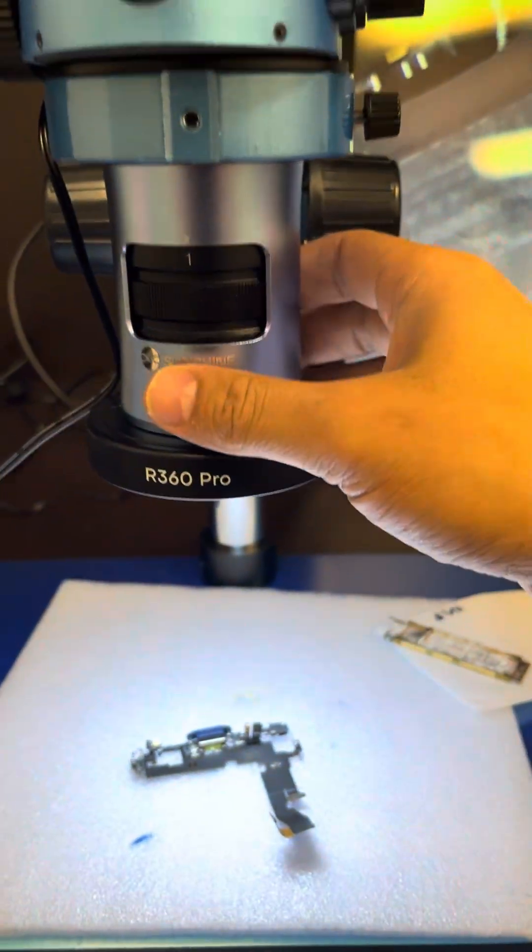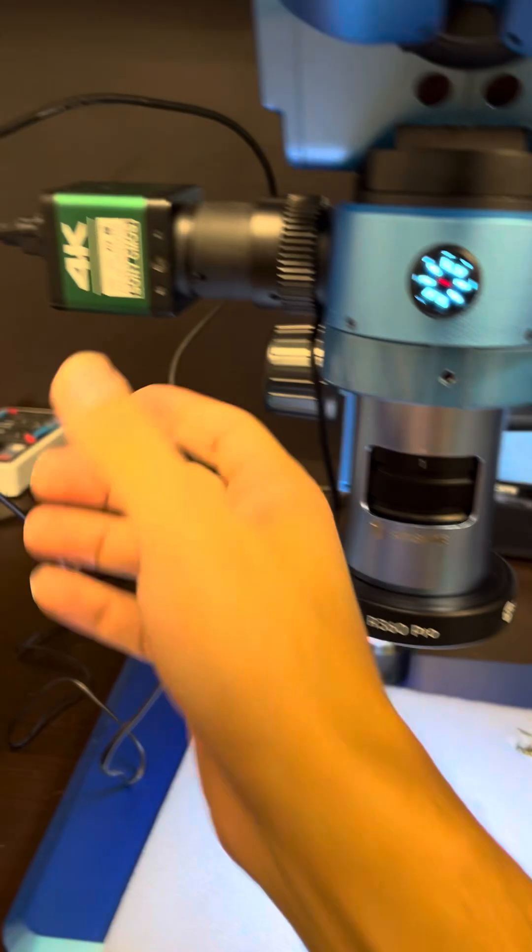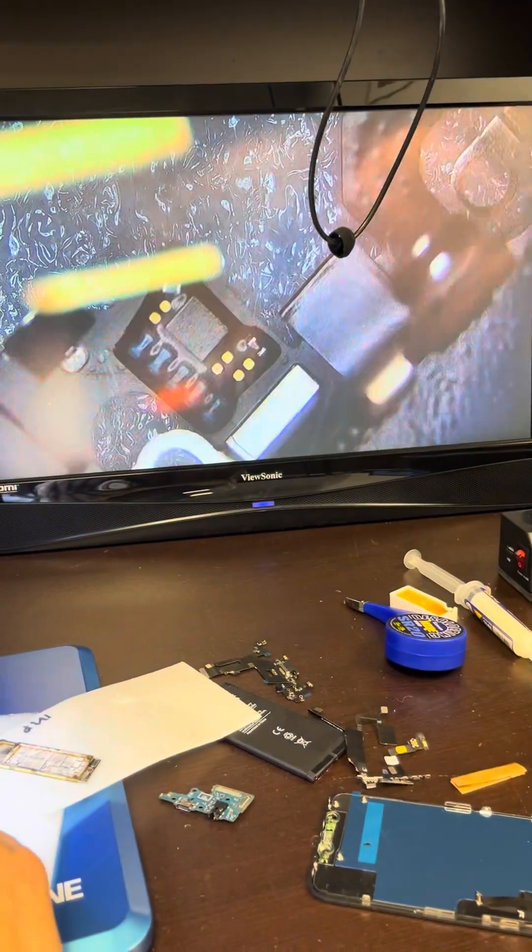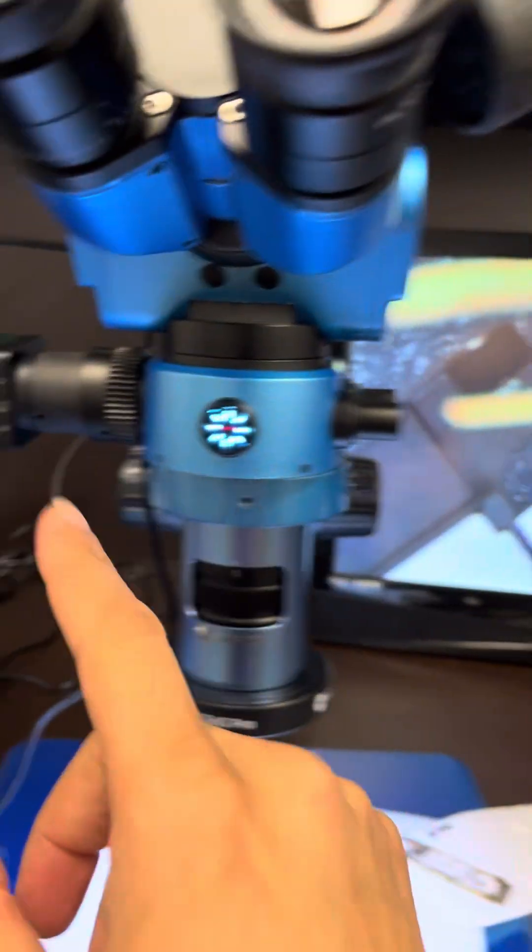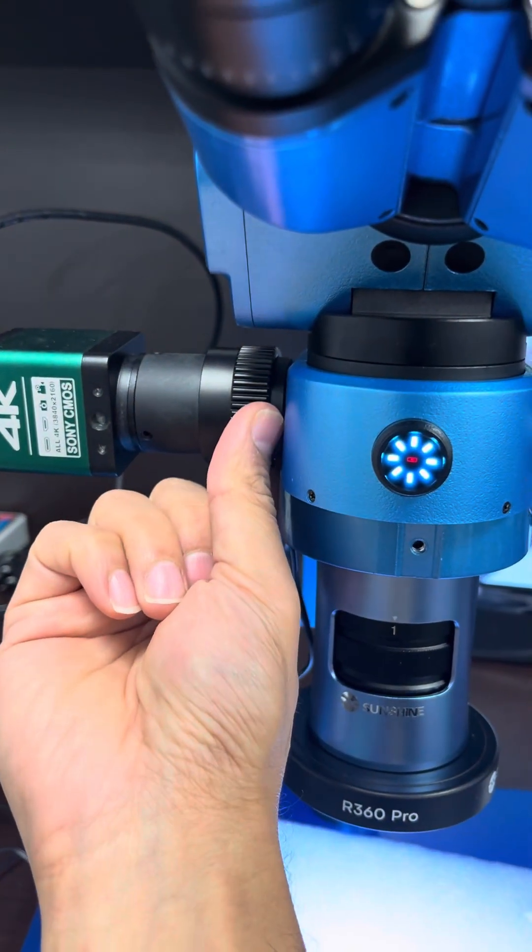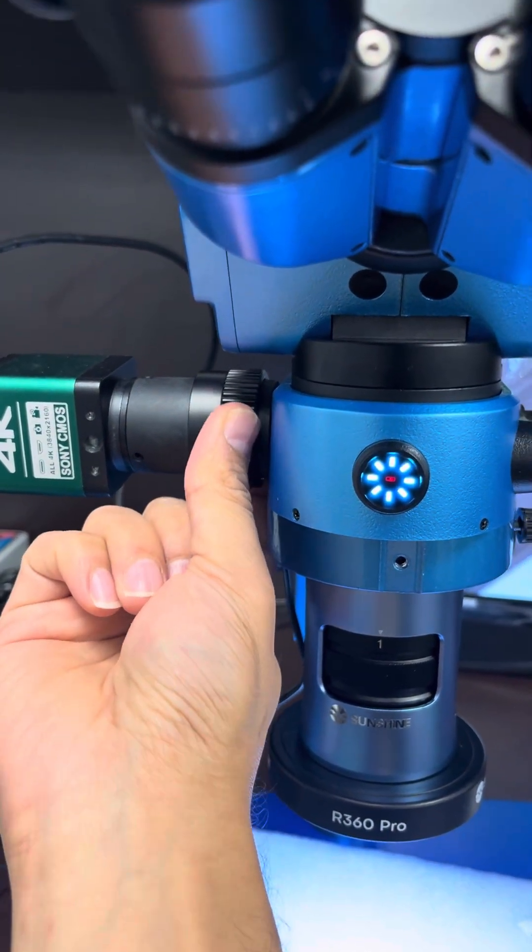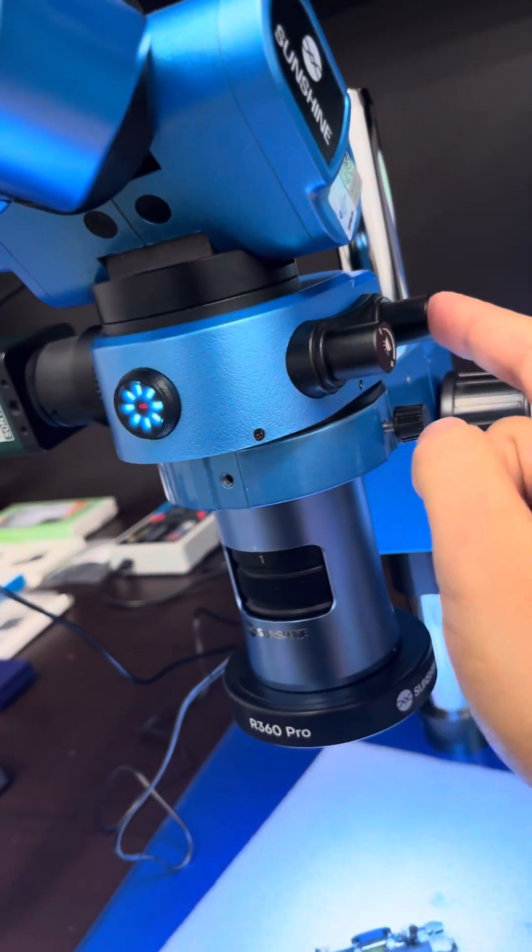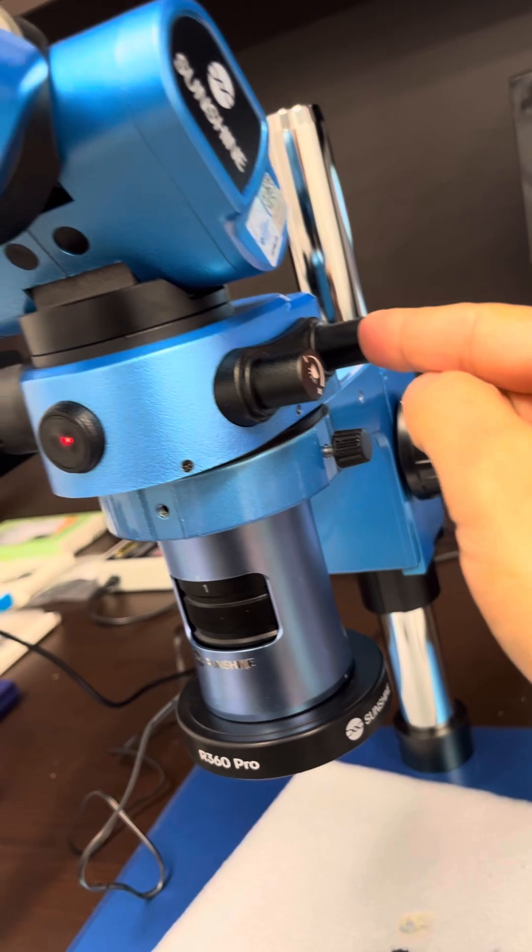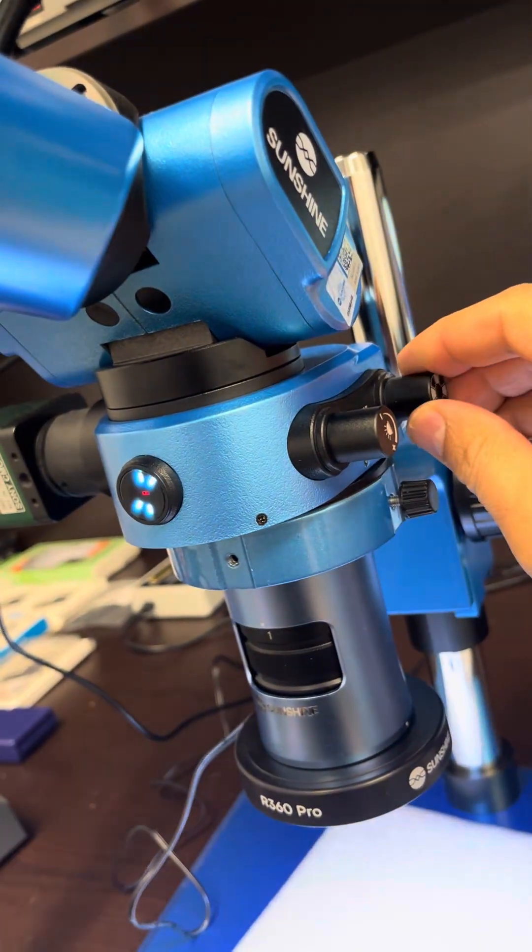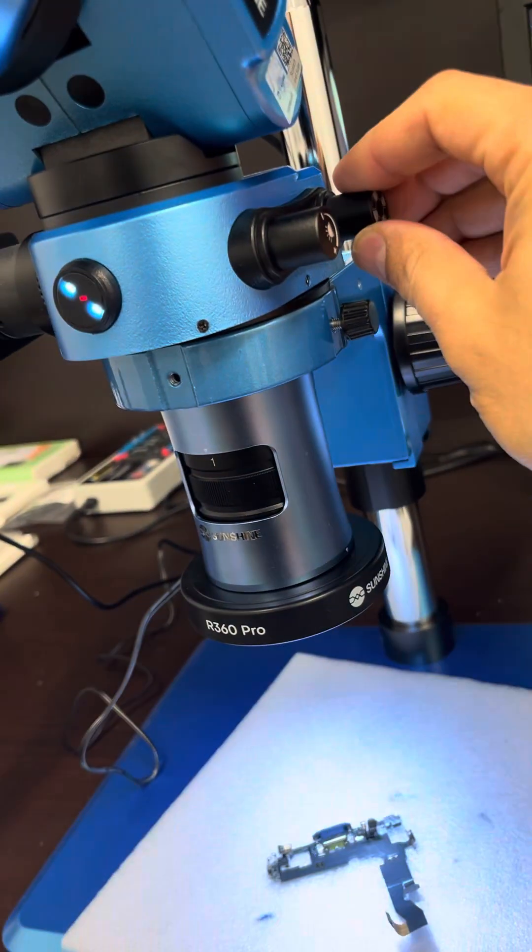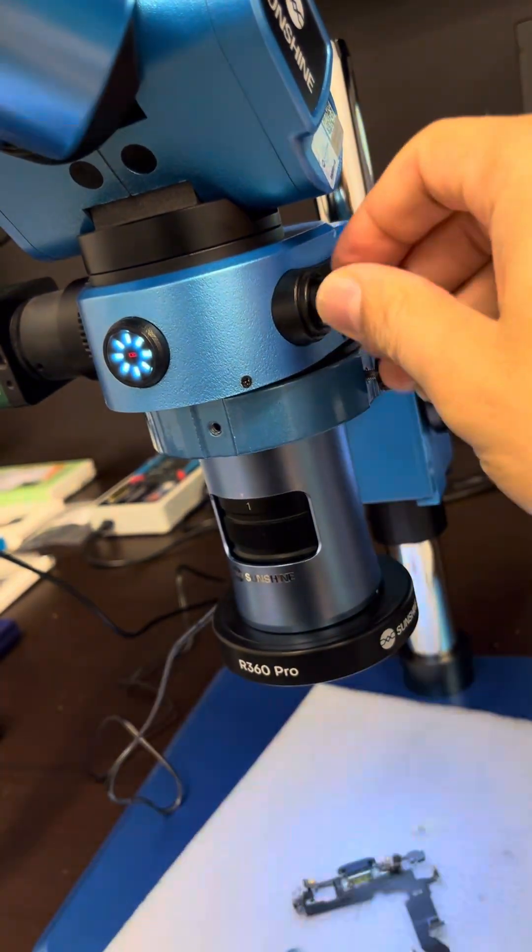If your microscope is focusing on the object but you have a camera and there is no good focus on the display, there is another magnification lens here. So you have to use this area to make a focus on the TV. Other thing about this microscope, you can turn on the light with this switch - you have to press it inside. You can change the direction of the light, you can increase the brightness.